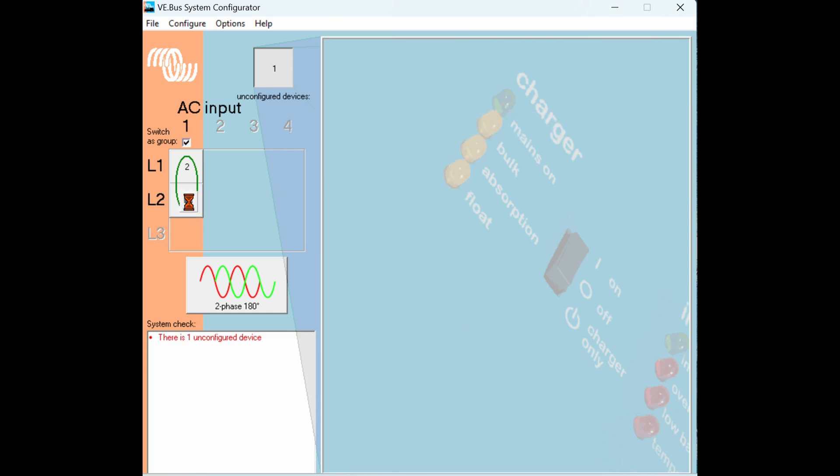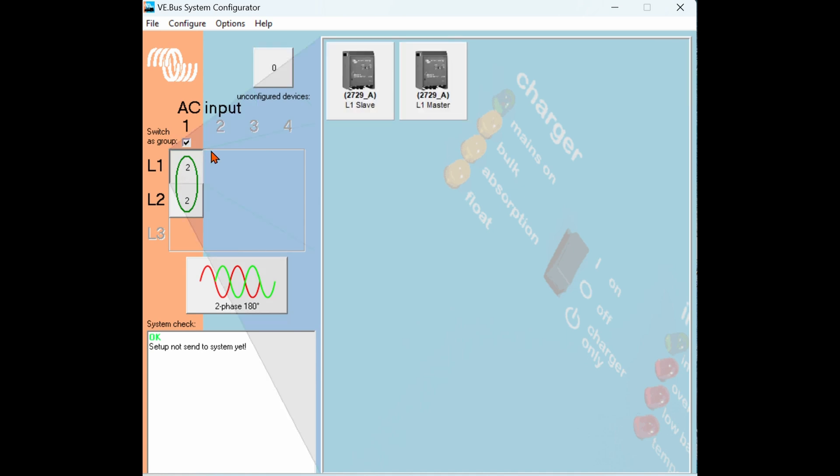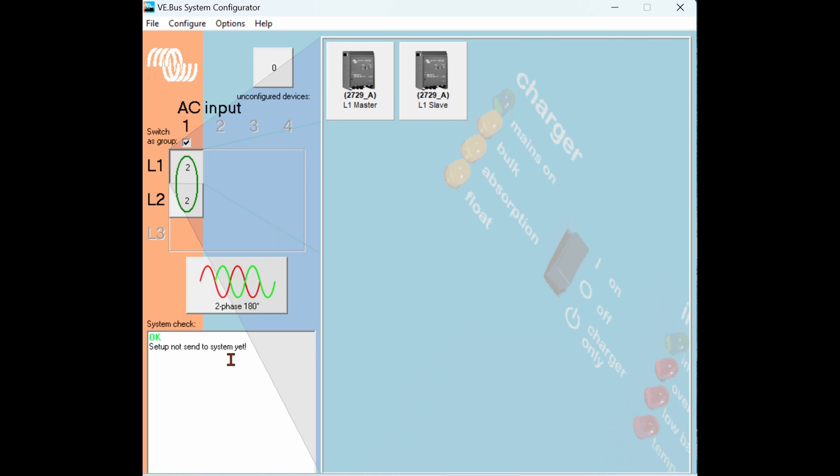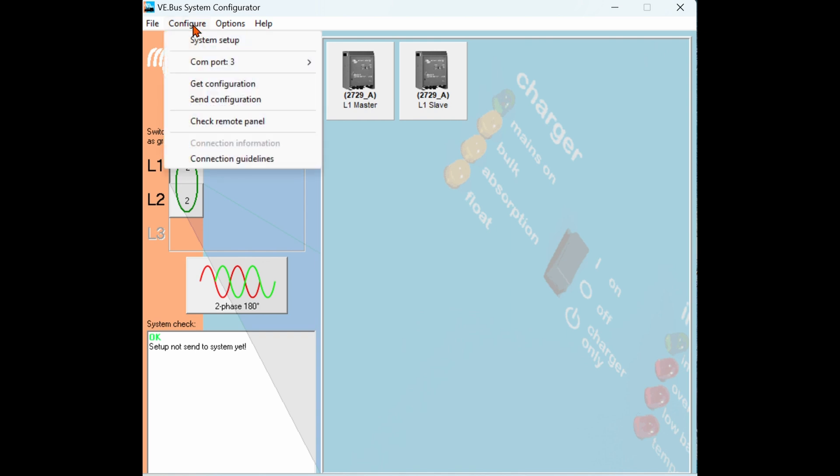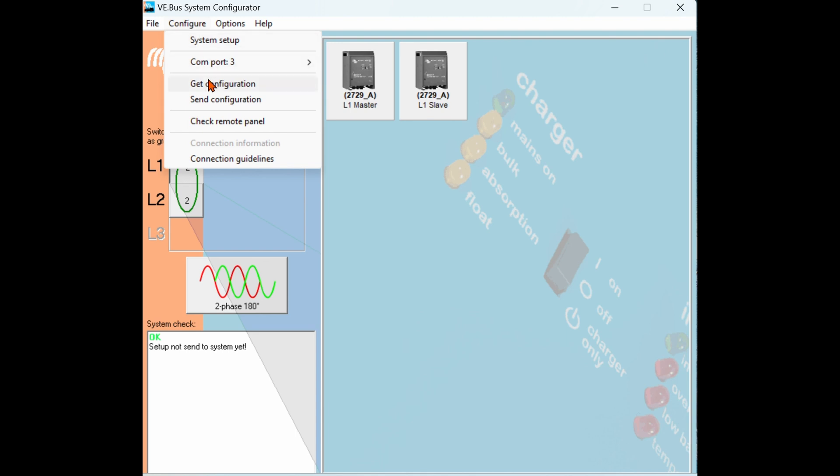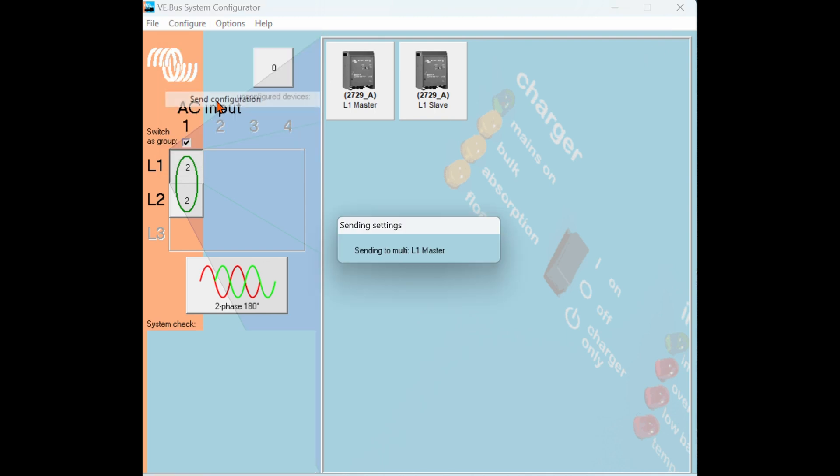Once we drop them in we can click on the given phase and see the phase order. We want to be sure that the slave inverter is second and the master inverter is first, and we can always swap that order by dragging them around. Final step now is to just double check both phases and the positions of all the inverters are correct. So by checking L1 and those positions and L2 and that we have no unconfigured devices. Triple check our phase configuration and then we're going to go up to the top here to configure and we're going to choose send configuration. That's going to take our currently configured layout and push it to the inverter system.